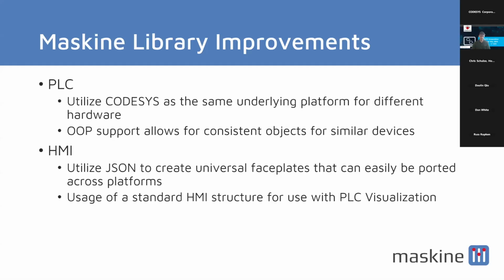Inside of that PLC library, what we've done is: anytime a command over JSON is received by the PLC, it takes that command and writes it to the HMI command structure, and then that goes into the logic. So everything is handled in a very clean way, allowing for a streamlined, consistent, and simple way of handling commands, status, and configurations.